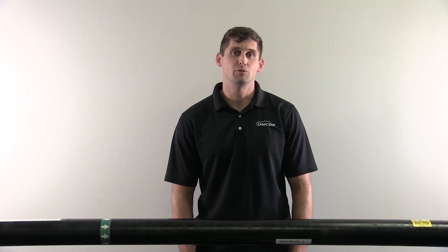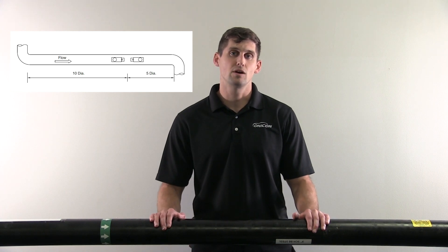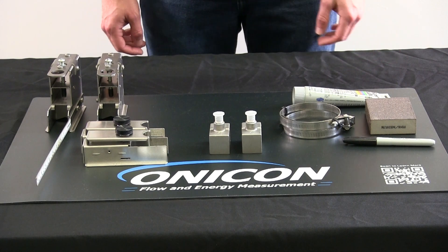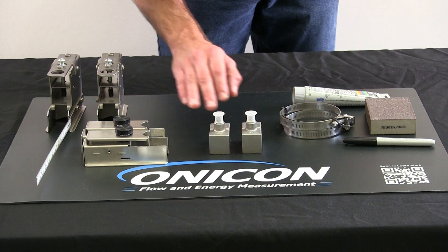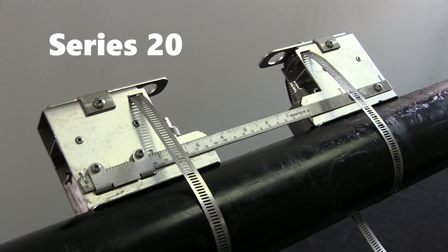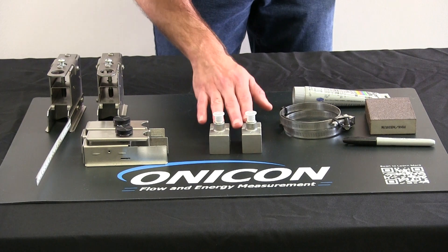The first thing you're going to want to do before you get started is make sure that you've located a straight length of pipe that meets the requirements in the meter manual. With every meter comes installation hardware along with a transducer and bracket pair. There are three different styles of brackets and transducers depending on your pipe size. Today we'll be dealing with the series 20 transducers and their brackets.